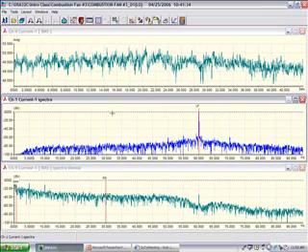Next thing I'm going to point out, there's my line frequency. You can see there's very little in the way of peaks down here. There are some sidebands based on running speed. It has selected a running speed. There is a small pole pass frequency. There are these two peaks all the way to the left, one at about 5 hertz and one at about 10 hertz. This is a fan application, and I normally see pump impeller-related issues and fan-related issues in that range. How to calculate that? I don't think anybody's figured that out yet. We're still working on it.